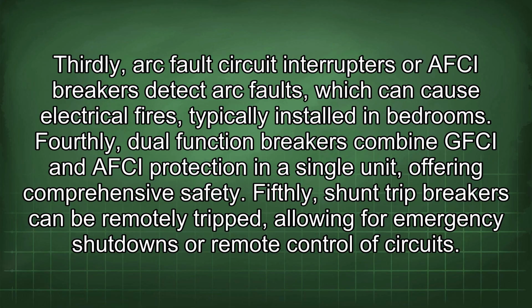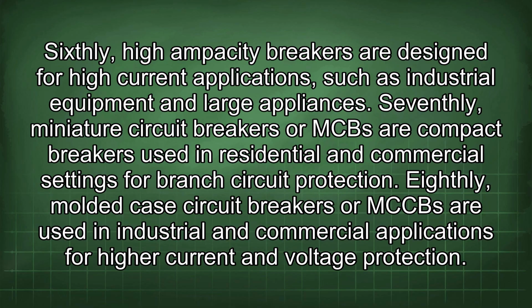typically installed in bedrooms. Fourthly, dual function breakers combine GFCI and AFCI protection in a single unit, offering comprehensive safety. Fifthly, shunt trip breakers can be remotely tripped, allowing for emergency shutdowns or remote control of circuits. Sixthly, high-ampacity breakers are designed for high-current applications, such as industrial equipment and large appliances. Seventhly, miniature circuit breakers or MCB are compact breakers used in residential and commercial settings for branch circuit protection.